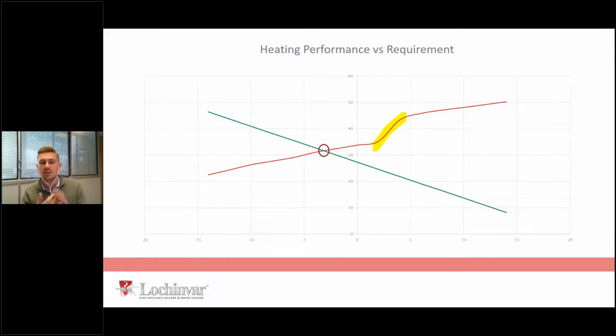And when that turns to ice, it slowly builds up and it will restrict the airflow across the evaporator. And when you restrict your airflow across the evaporator, you affect the unit's efficiency. And if you affect its efficiency, your electric input always stays the same. The efficiency determines your output. Well, if the efficiency drops, your output drops, which is why as you get into these lower temperatures, or certainly this defrost zone, you get the drop off in performance. So this is the time when basically, like this morning, it was probably in this range for a long period of time. You could have expected that heat pump to possibly go into its defrost function for a few minutes, just to melt the ice on that evaporator, get rid of that ice and go back to its normal function of heating.